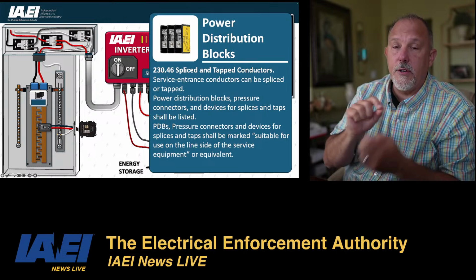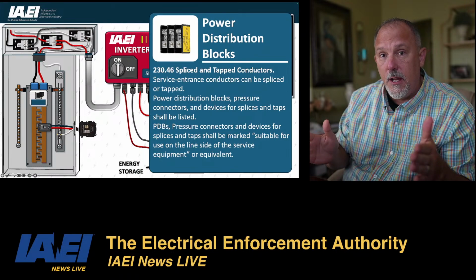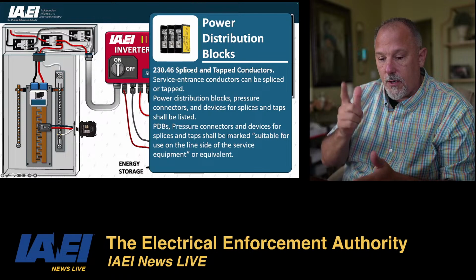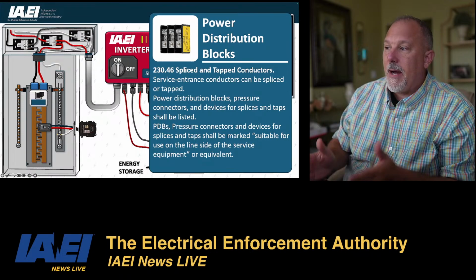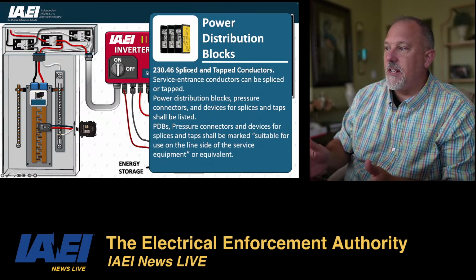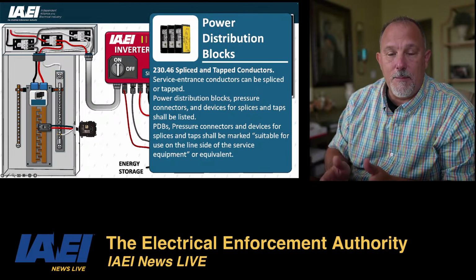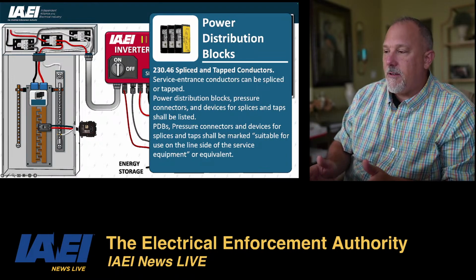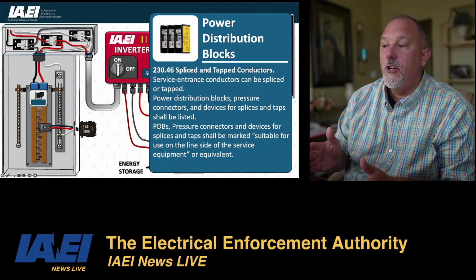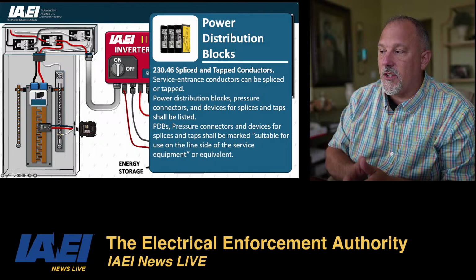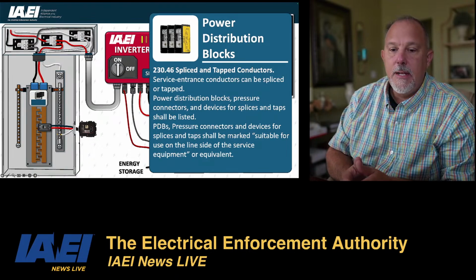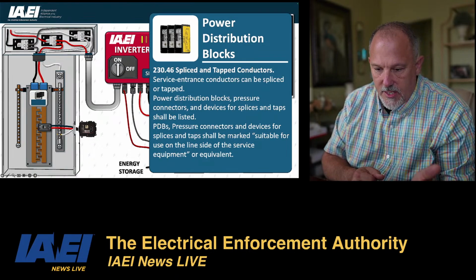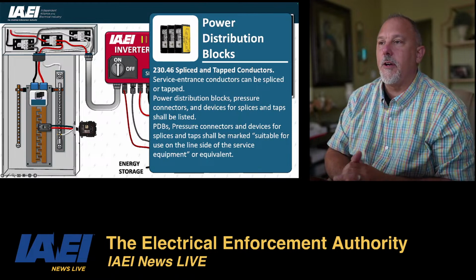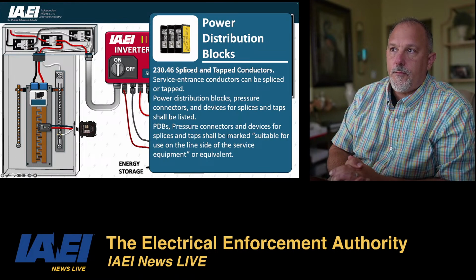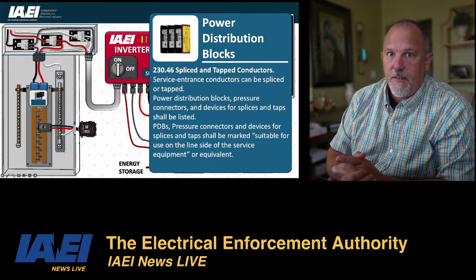So it's very important to understand the distinction and the definitions of what all of those conductors are, and we're going to review those. Power distribution blocks, pressure connectors, and devices for splices and taps shall be listed. And the power distribution blocks and the connectors and those devices for splices and taps shall be marked suitable for use on the line side of the service equipment or equivalent. Now, Robert says distribution blocks rated for fault current. So they need to be rated for fault current.